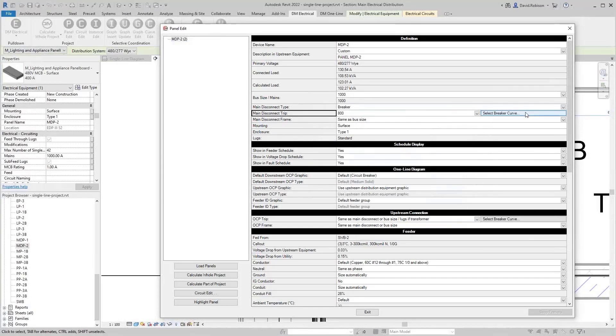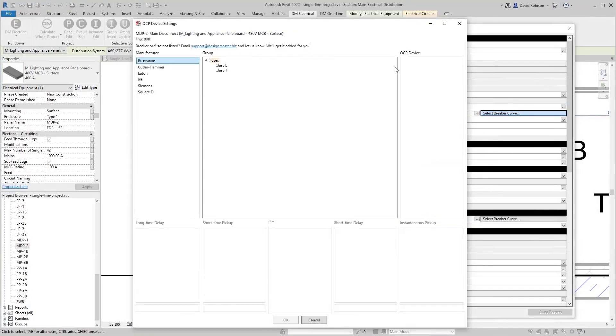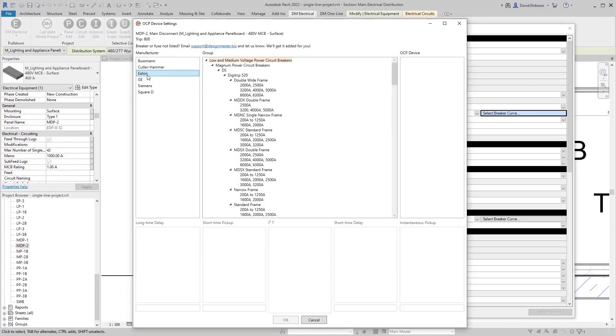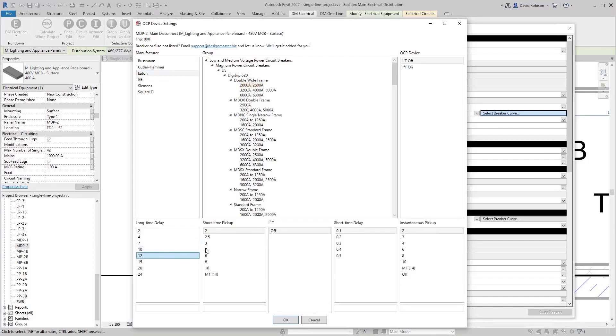The select breaker curve button lets you choose the specific breaker associated with that main disconnect. We use this for arc flash — finding trip times — and for selective coordination graphs. You only need to set this if you're doing selective coordination or arc flash; otherwise you can ignore it, as other calculations like fault and voltage drop don't depend on the specific breaker curve.